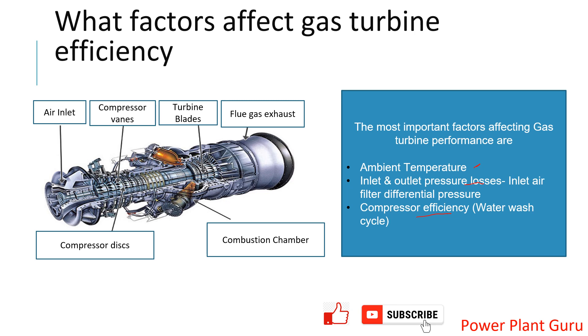We know that gas turbines usually take a lot of air for functioning. When you have ambient temperature lower than normal, the density of the air at that temperature will be higher compared to higher temperatures. Lower temperature definitely means higher density. So in the same volume, you are pushing more quantity of air, and as you push more air, you can inject more fuel as well. In turn, you get a higher output. Higher density of air is the deciding factor.